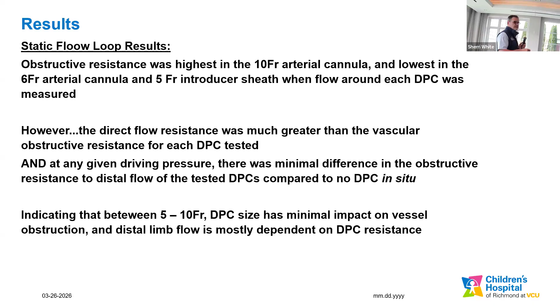However, the direct flow resistance was much greater than the vascular obstructive resistance for each of the distal perfusion catheters tested. And at any given driving pressure, there was really minimal difference in the obstructive resistance to distal flow of any of the tested distal perfusion catheters compared to having no distal perfusion cannula in situ. So adding a distal perfusion cannula, regardless of which model or which size you use, really doesn't add any significant degree of vascular obstruction to the overall delivery of flow to the distal limb. So what that indicates is that anywhere between a 5 and a 10 French, the distal perfusion cannula size has minimal impact on vessel obstruction, and the distal limb flow is mostly dependent on the internal distal perfusion catheter resistance.